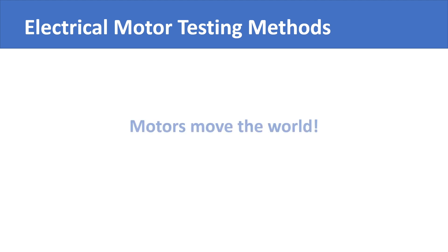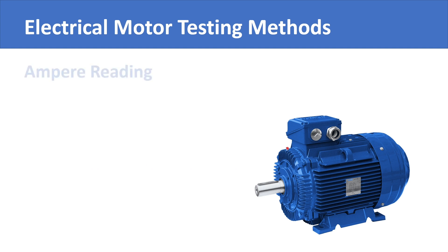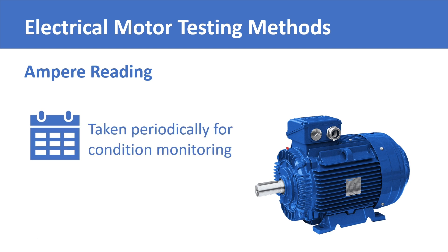Motors move the world. Therefore, maintenance and reliability professionals are supposed to know about electric motors as well as some common techniques used for monitoring their condition and testing them. The simplest way of telling if something is wrong with a motor is to simply test the current it is drawing from the supply. This reading can easily be taken on a daily, weekly, monthly, or any other time interval to reveal any hidden developing defects inside the motor.